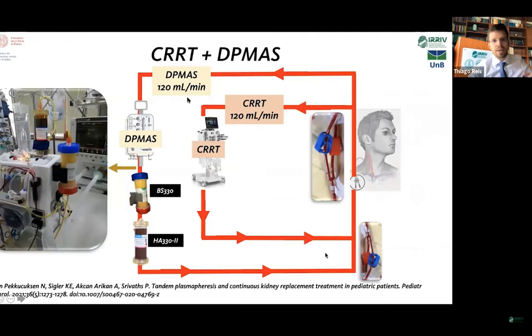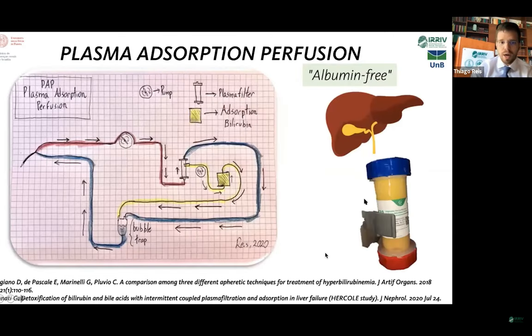We can also apply both therapies — DPMAS and CRRT — in parallel at the same time. We can place a Y connector in the arterial line of the catheter, and simultaneously 120 mls per minute of blood going through the CRRT circuit — for example in a patient with hyperammonemia — and in parallel, 120 mls per minute going through the DPMAS circuit. They then return to the patient through another Y port.